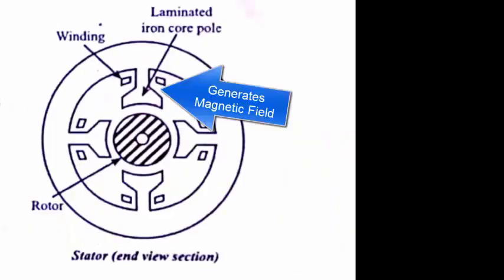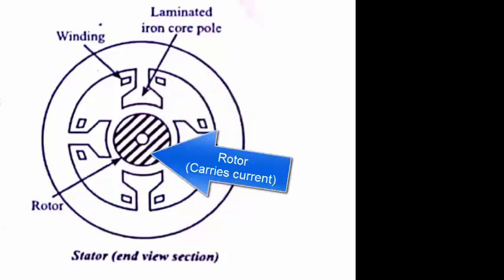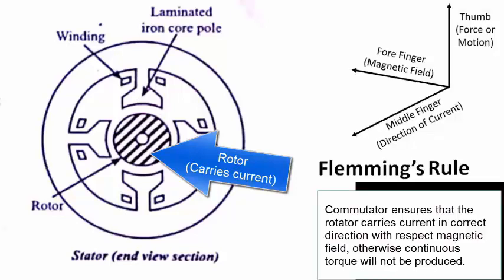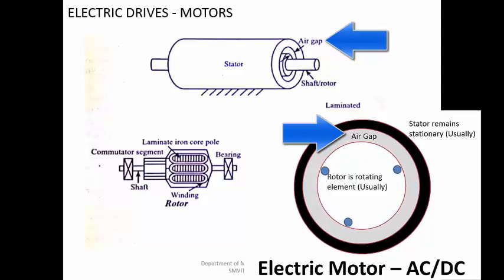This is a cross-sectional view. Here you have the coil and the soft iron core. Soft iron is a ferromagnetic material that can generate a very good magnetic field. This is the rotor, which carries the current. You have the magnetic field and the current-carrying conductor, and because of their interaction, a Lorentz force is created trying to rotate the conductor. The conductor is pinned about the central shaft. There is a small air gap between the rotor and the stator coils — if too large, the magnetic flux may not be sufficient; if too small, frictional effects and rubbing can cause sparks and wear and tear.